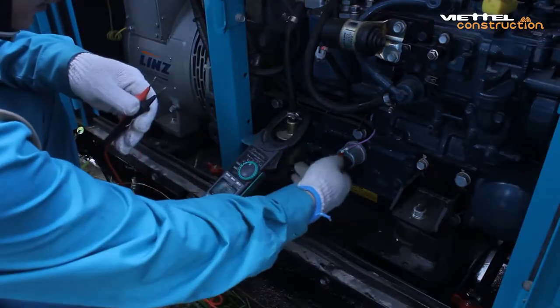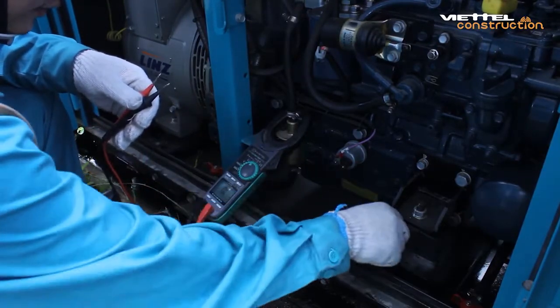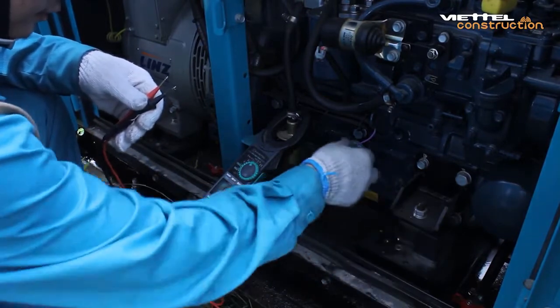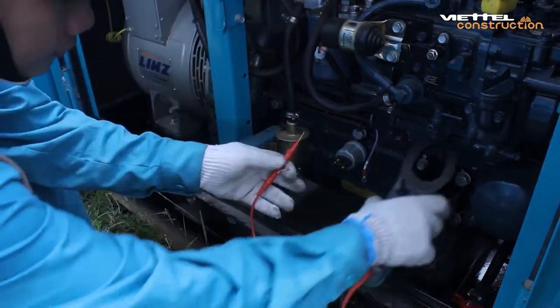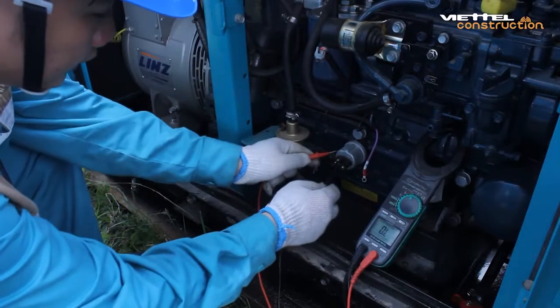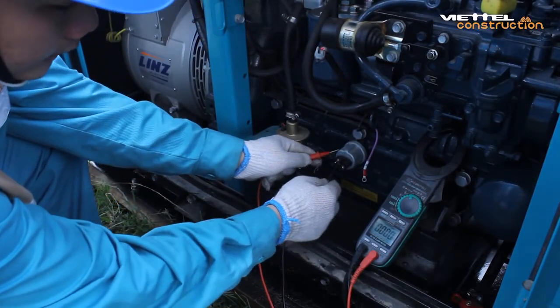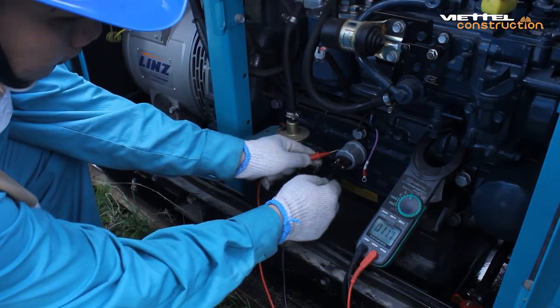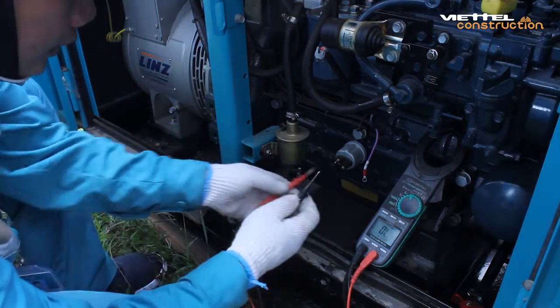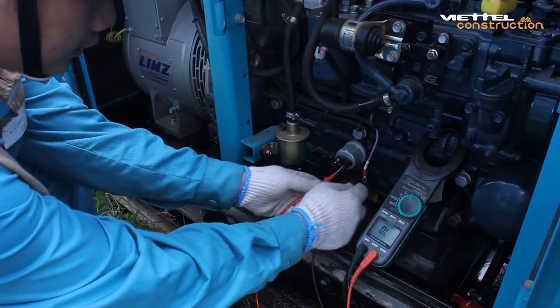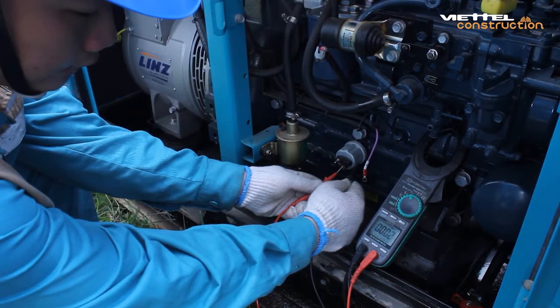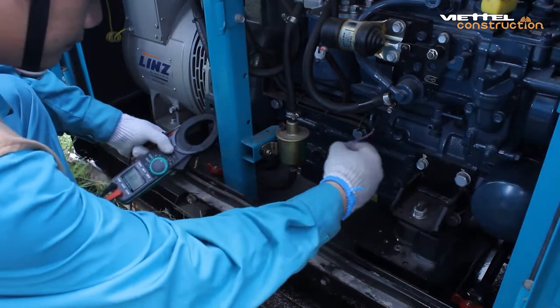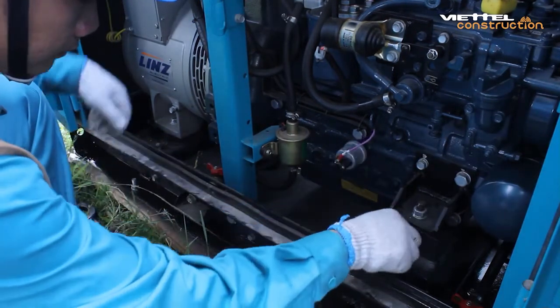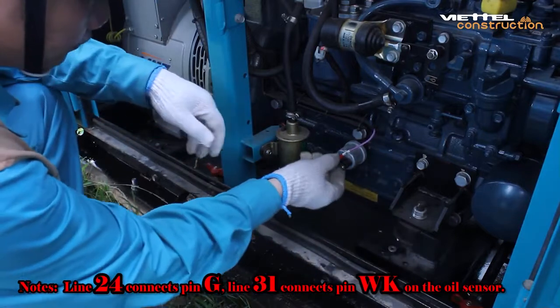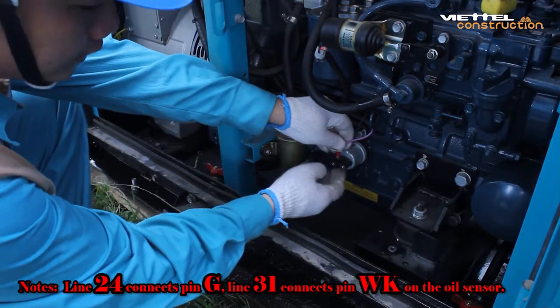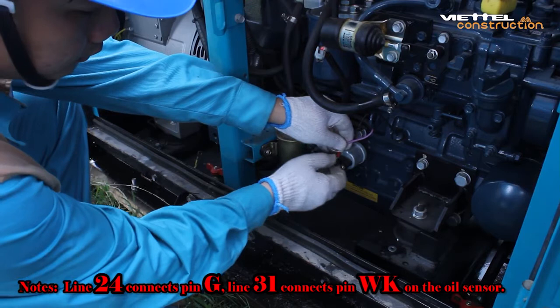Check the performance of the oil sensor connection line. Proceed to remove the oil sensor contact. Measure the oil sensor with the ground of the machine, it must reach 8 to 10 ohm. If higher, proceed to remove oil, if lower, then add oil. Measure the remaining point of the sensor with the common ground, normally closed is reached. Reassemble the wire into the sensor and tighten it. Note: line 24 connects pin G, line 31 connects pin WK on the oil sensor.